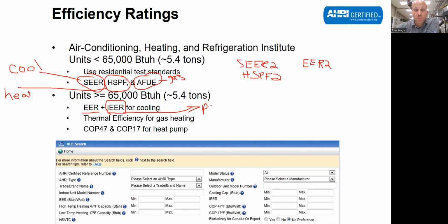This is a significantly more important number than full load because you're almost never at full load. So I don't care if this thing's a dog when it's 95 degrees outside. I want to know how efficient it's going to be at 90, 89, 91, 87. That's more important to me than 95 because 95 hardly ever happens. That's where the IEER comes in. What they do for IEER is they test it at 25, 50, 75, and 100% loaded. 100% means it's the regular EER.